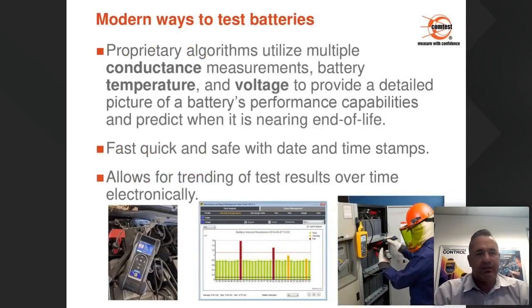Modern ways to test the batteries. We use proprietary algorithms to utilize multiple conductance measurements, battery temperature, and voltage to provide a detailed picture of a battery's performance and predict when it's nearing the end of life. Fast, quick, and safe, with date and timestamps, and it allows for trending of test results over time electronically. So in this slide, if we have a look at the graph in the middle, it is so easy to see which batteries are failing. Just by looking at that picture, it's a quick overview of what's happening. In that case, each and every battery in those strings was tested individually, and for argument's sake, battery number 15, you can see that the internal resistance is different from the rest.